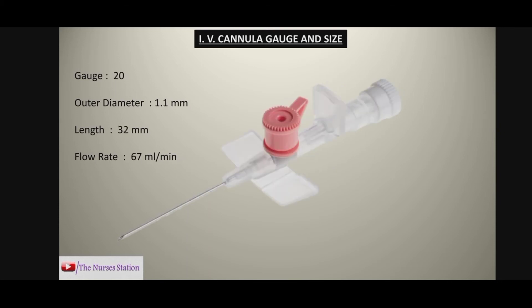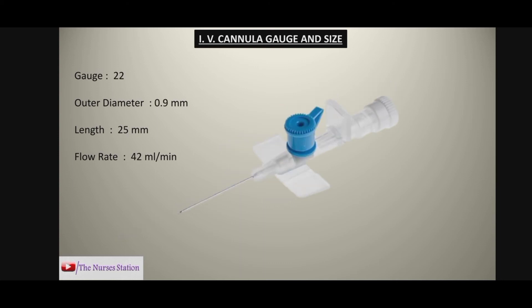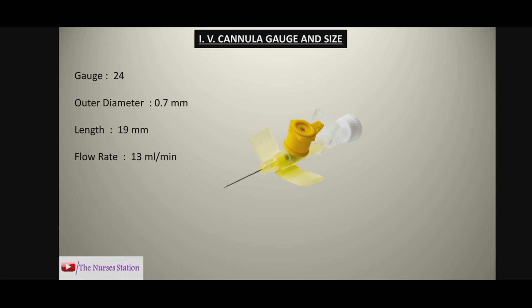Next is the pink colored cannula with a gauge size of 20, outer diameter of 1.1 mm, length of 32 mm, and a flow rate of 67 milliliters per minute. The blue colored cannula has a gauge size of 22, outer diameter of 0.9 mm, length of 25 mm, and a flow rate of 42 milliliters per minute. Then we have the yellow colored cannula with a gauge size of 24, outer diameter of 0.7 mm, length of 19 mm, and a flow rate of 13 ml per minute.